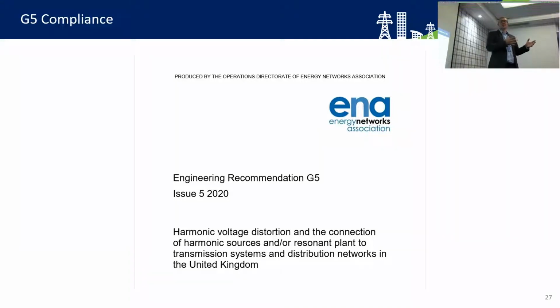If anybody is going into any commercial agreements with manufacturers from abroad, before you sign on the dotted line, I'd be going to them and saying, can you confirm that it complies with parts of G5? Just because it complies with G5 doesn't mean it can be connected, because we have to do assessments on the grid. I'll go through one in a minute where we calculate the fault level and then pro-rata it, it's a straightforward and easy calculation to do. But if you can't confirm that it's compliant with such a standard...